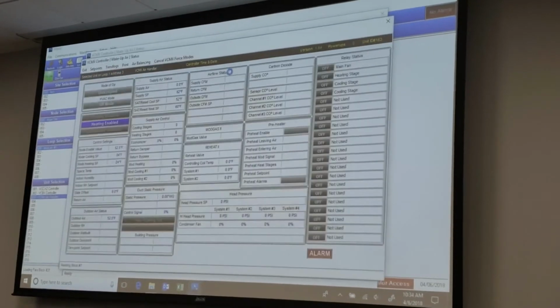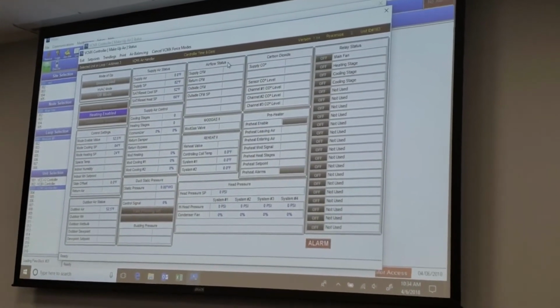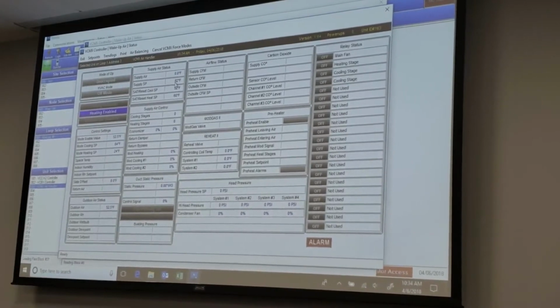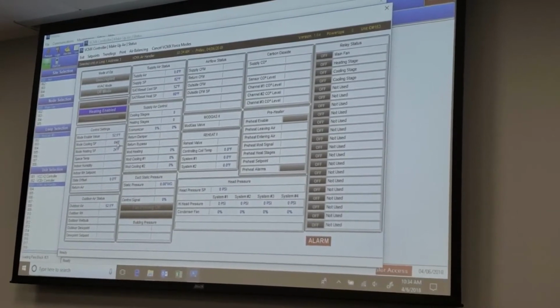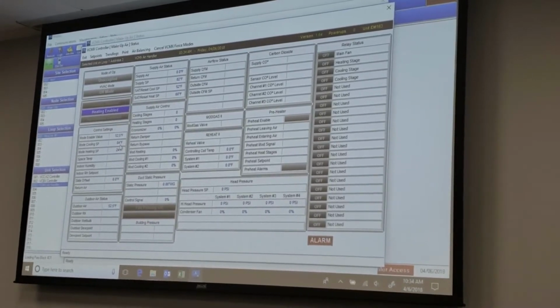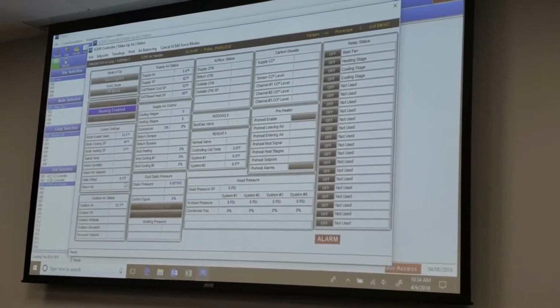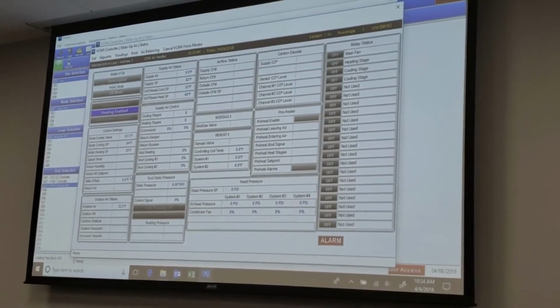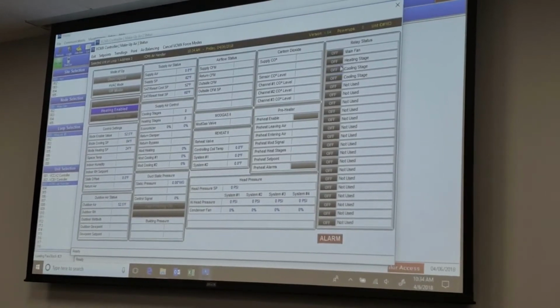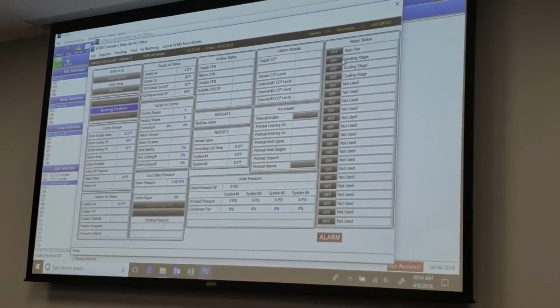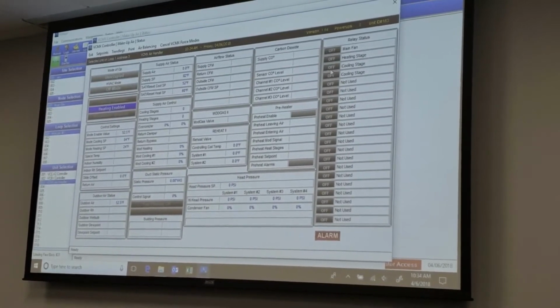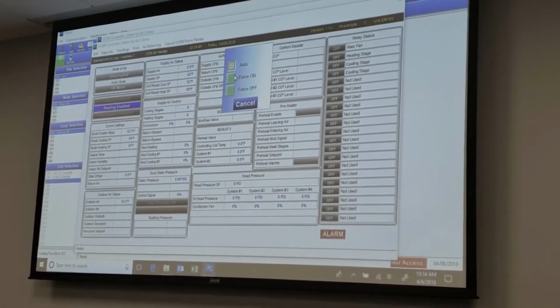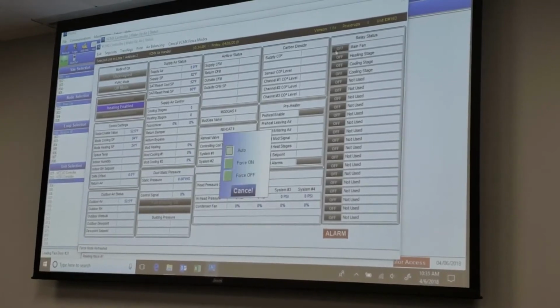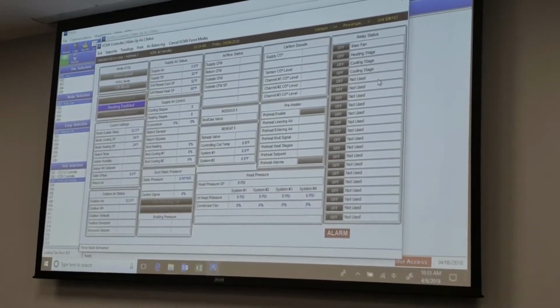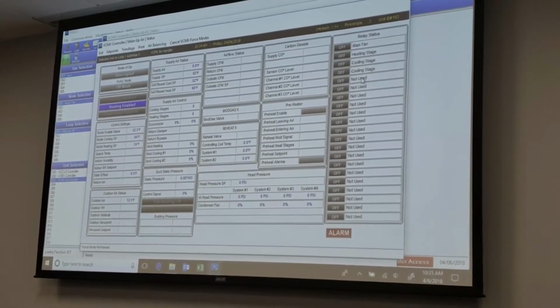Got your detail viewer. That's everything that unit is doing in one screen. So I got my supply air temperature set point, reset, enable value, whatever the enable temperature is, cooling set point, heating set point, space temperature, indoor RH, dew point, outdoor dew point. So it gives you everything on one screen. You can actually come in here, like right now, I got these relays assigned as heat stages, and a couple cool stages here. I could actually go in here, click on this, and force this relay on. And let's say I want to go in here and force my fan on also. And y'all hear him click here in a second. Yep, there went one.